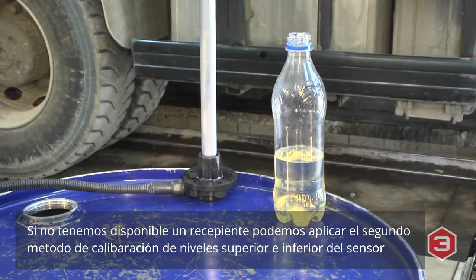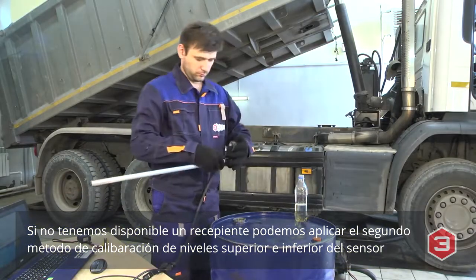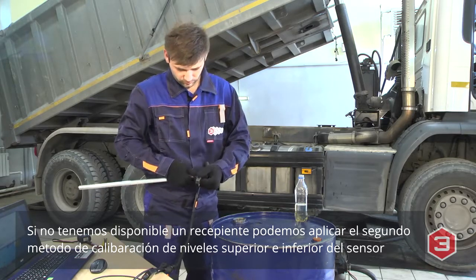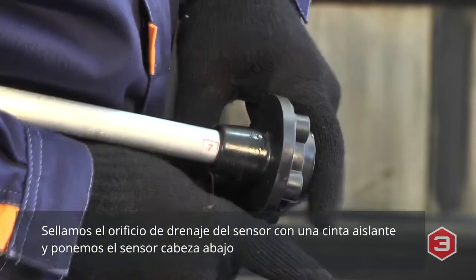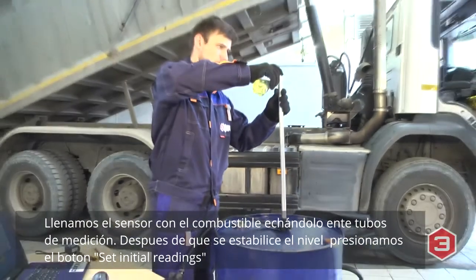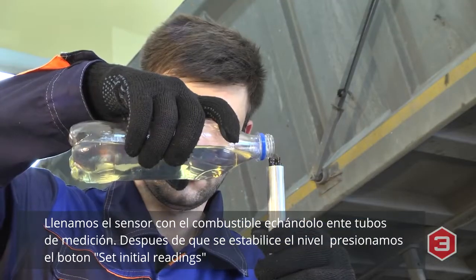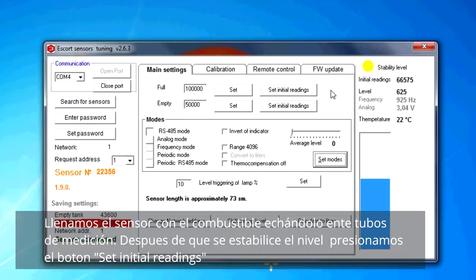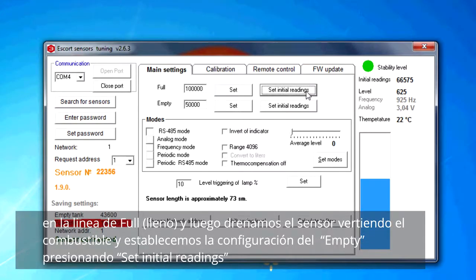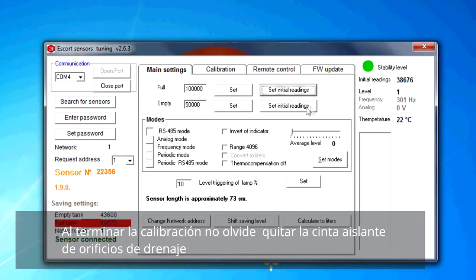If you don't have any container, use the second way to set upper and lower levels. Close up the drainage hole at the sensor bottom with tape and turn the sensor flange down. Fill the fuel between the measuring tubes and after the level stabilizes, calibrate the full condition. Drain the fuel and calibrate the empty condition. After the calibration is finished, do not forget to remove the tape from the drainage hole.